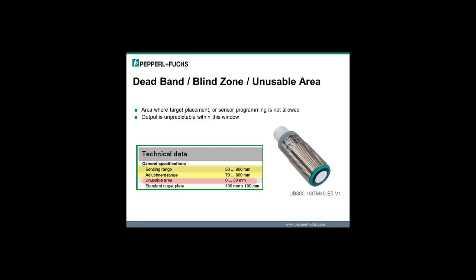The unusable area is also called by some manufacturers the dead band or the blind zone, but it's an area where target placement or sensor programming is not allowed. The output can be unpredictable in this window. The way the sensor works, it sends out an ultrasonic pulse and waits for it to come back, and there's a ringing involved. The transducer needs to stop ringing so it can accurately hear the echo return. If you're too close, the transducer is still vibrating and it's going to have some stability issues and not be able to hear that echo pulse return.